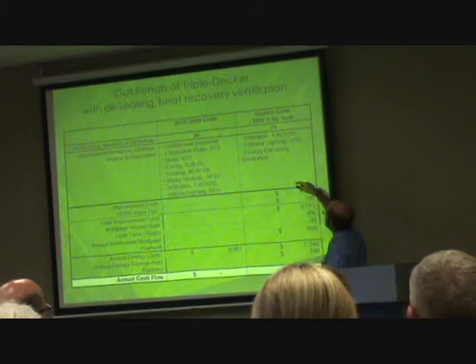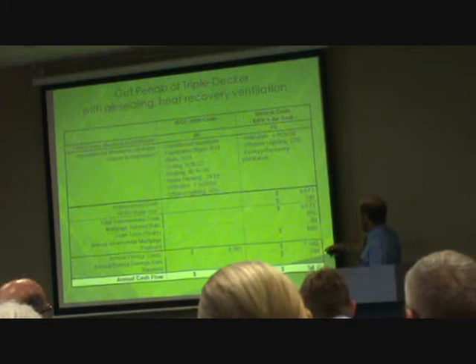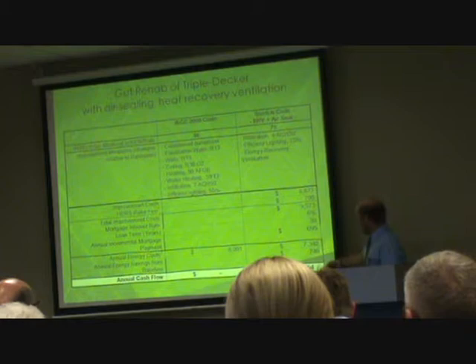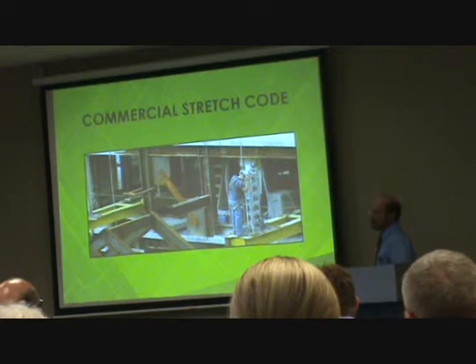In that scenario, we've reduced infiltration to four air changes per hour and put in the energy recovery ventilation system. The improvement costs are a lot higher, and the annual energy savings are also a lot higher — but you still get fairly small savings overall. For gut rehab, we actually think most of the savings comes from what the base code is going to require anyway.